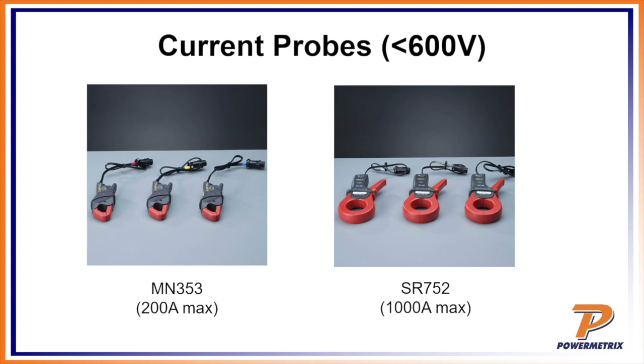So right now what we're using here are what we call MN353 probes, and those are 200 amp max rated. Now if you had a class 320, this may not work, right? Right, that's correct. But a lot of the 16S meters are class 200, so these type of test switches, these type of clamp-on probes will work fine.